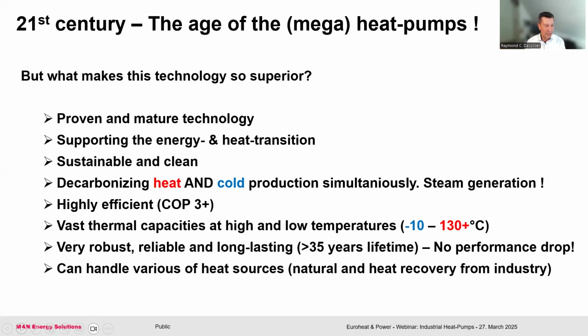They are sustainable and clean, decarbonizing heat and cold production simultaneously, and they can even generate steam for steam district heating networks. They are highly efficient: a COP of 3 or more is achievable on the hot side. Adding the cold side, we can reach 5 or even 7 COP, an incredibly efficient technology. Compare that to an electric boiler, which has a COP of just below 1.